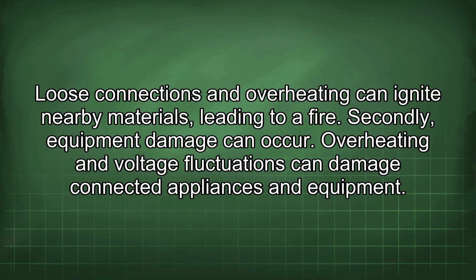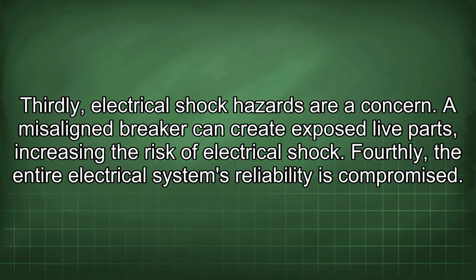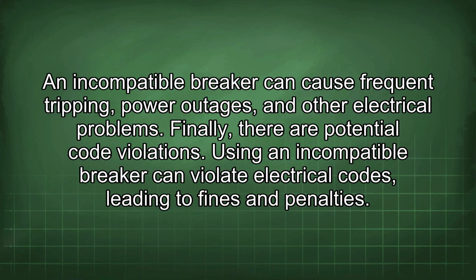Secondly, equipment damage can occur. Overheating and voltage fluctuations can damage connected appliances and equipment. Thirdly, electrical shock hazards are a concern. A misaligned breaker can create exposed live parts, increasing the risk of electrical shock. Fourthly, the entire electrical system's reliability is compromised. An incompatible breaker can cause frequent tripping, power outages, and other electrical problems. Finally, there are potential code violations. Using an incompatible breaker can violate electrical codes, leading to fines and penalties.